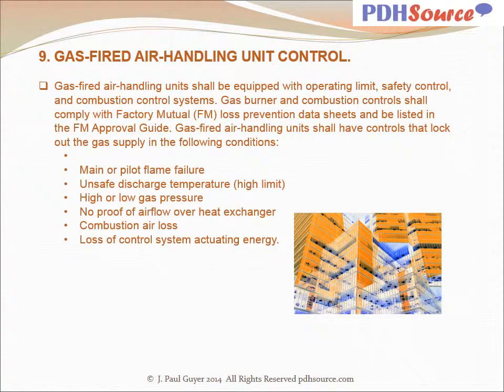Gas-fired air handling units shall be equipped with operating limit, safety control, and combustion control systems. Gas burner and combustion control shall comply with Factory Mutual loss prevention data sheets and be listed in the FM approval guide. Gas-fired air handling units shall have controls that lock out the gas supply in the following conditions: main or pilot flame failure, unsafe discharge temperature, high limit, high or low gas pressure, no proof of airflow over heat exchanger, combustion air loss, loss of control system actuating energy.